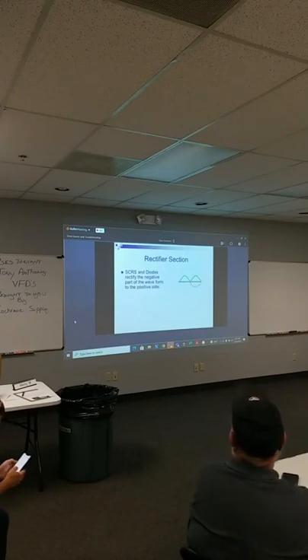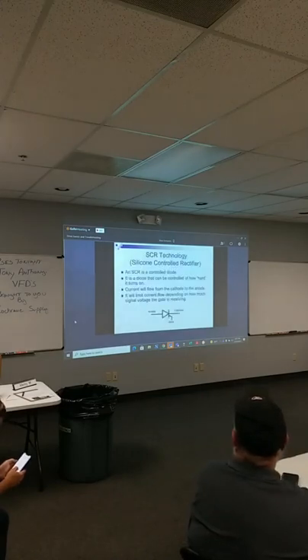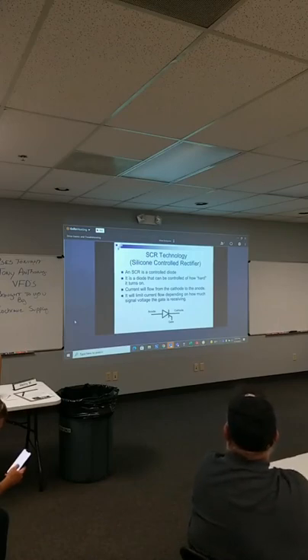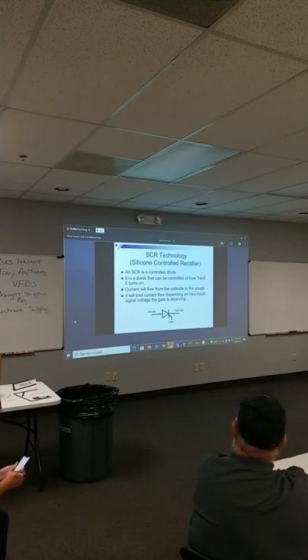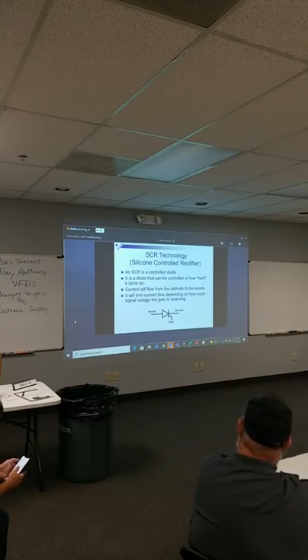Rectifier section, we're going to skip through some of this quickly. SCRs are old technology. This is what you still will see in soft starts. And the biggest difference between a soft start and a drive is, one, we can control the speed, you know, at any time we can vary the speed.